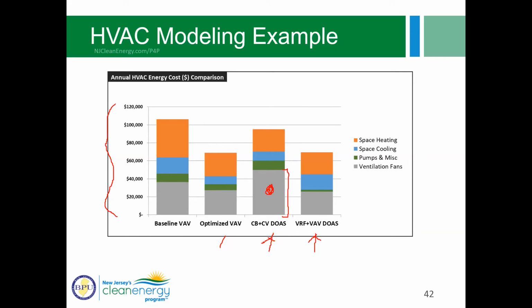What else? What else is interesting here? So I think another interesting piece is if we look at the variable refrigerant flow example, this guy, and we look at the cooling and compare it to the cooling with the optimized VAV, we see that there's significantly less cooling with the optimized VAV, which makes sense, right? Because you've got chillers with the optimized VAV, which tend to have a higher efficiency, especially the ones modeled here, than a DX variable refrigerant flow heat pump system. So that makes sense. And you're always doing that, right? When you conduct analyses, you're looking at the results and you're asking yourself, do these make sense? Is this what I expected, right?